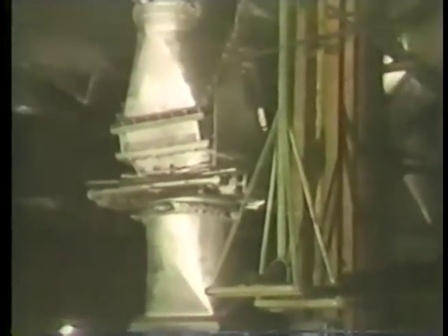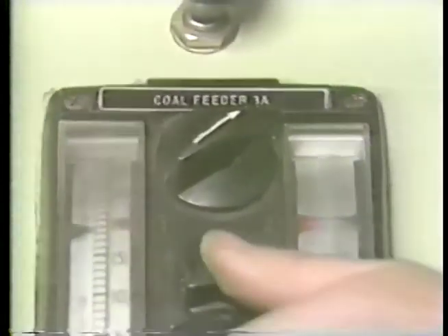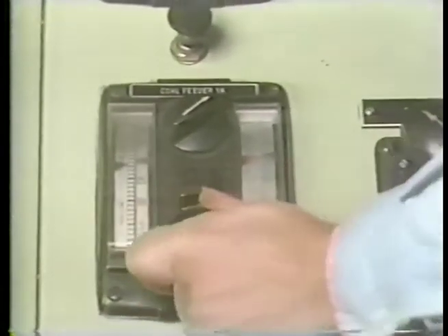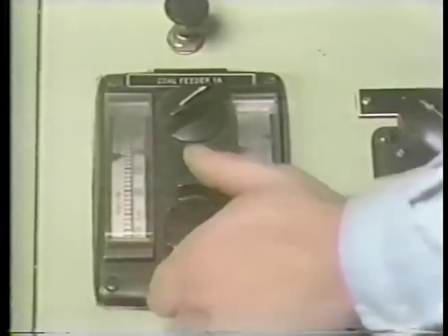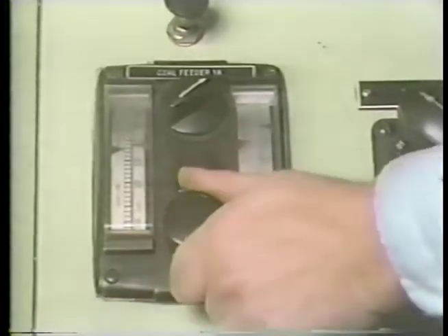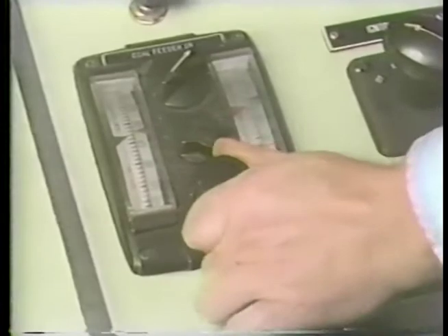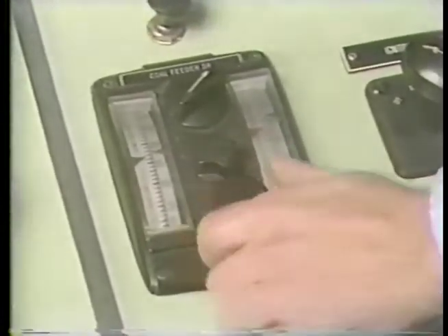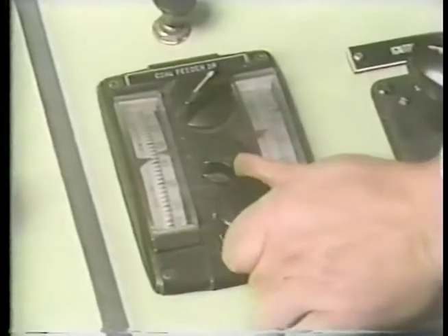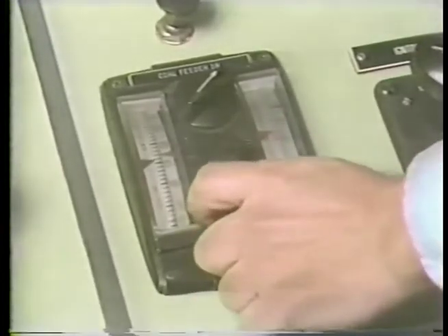The dried pulverized coal is carried to the coal burners by primary air. At the burners, the coal mixes with secondary air, forming a combustible mixture that is ignited by the igniters. The operator continues to adjust the supply of fuel to the burners by slowly increasing the flow rate through the feeders. When the appropriate fuel flow for the pulverizer is reached, the operator can repeat these steps with a second pulverizer if load demands call for it. The steps are repeated for all of the pulverizers that supply the boiler as demand requirements increase.